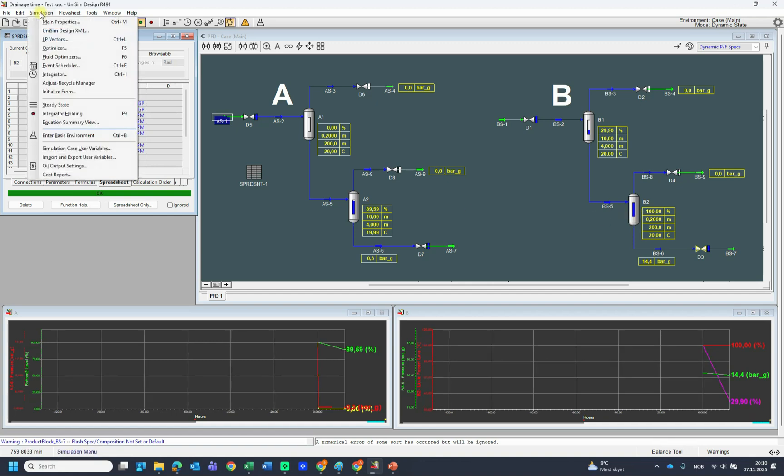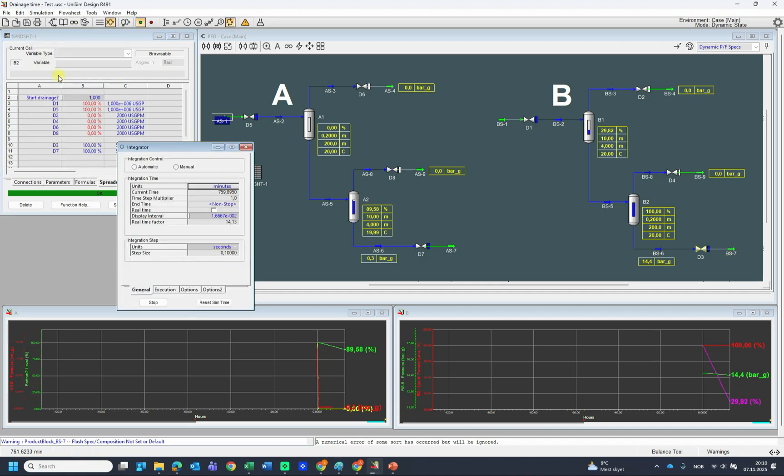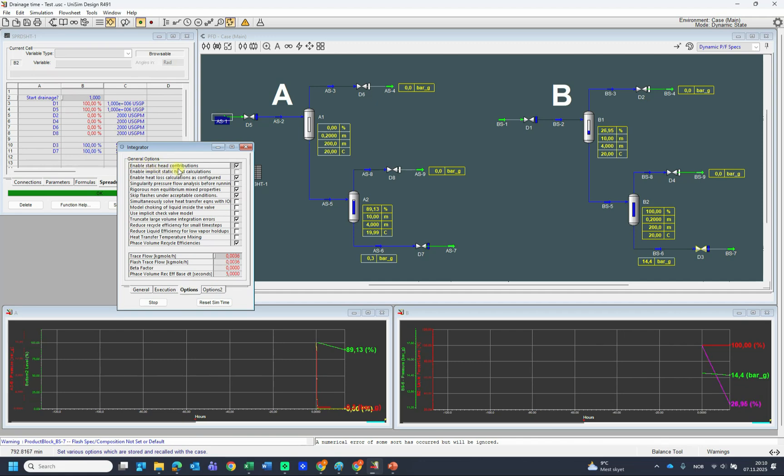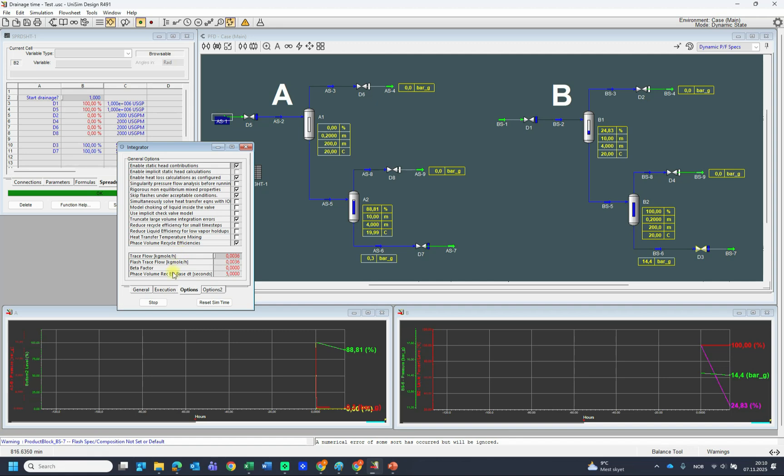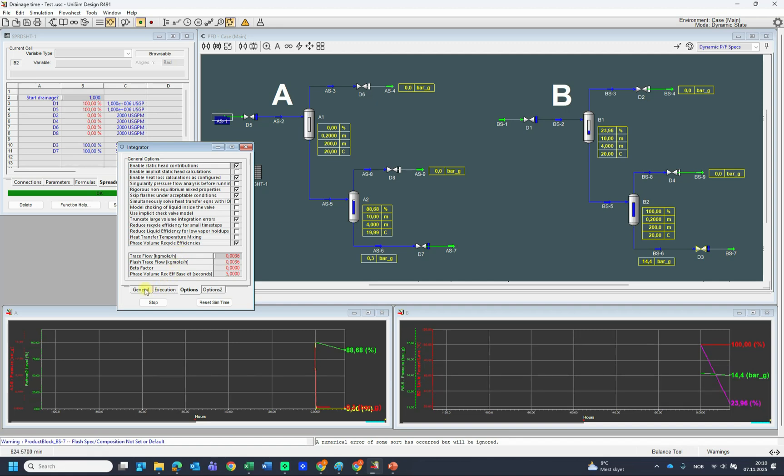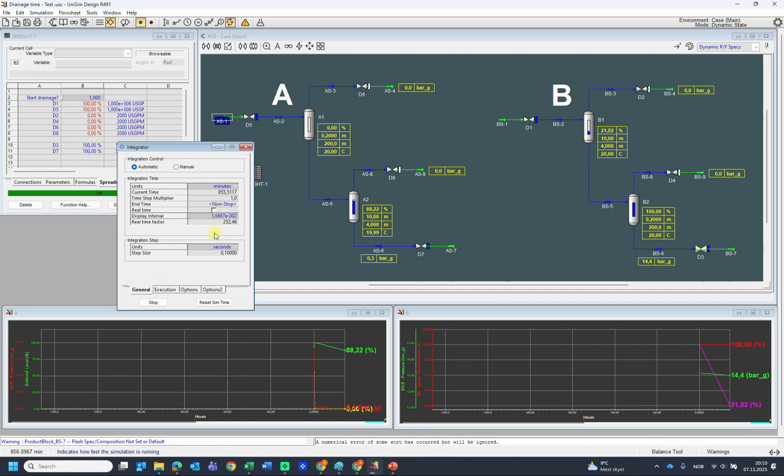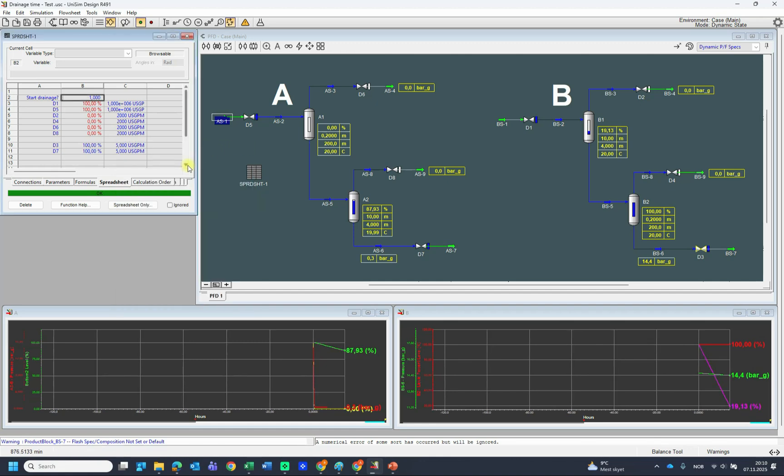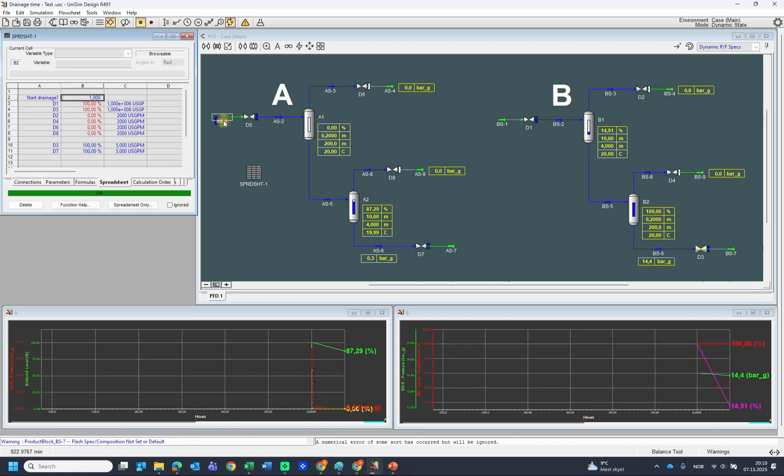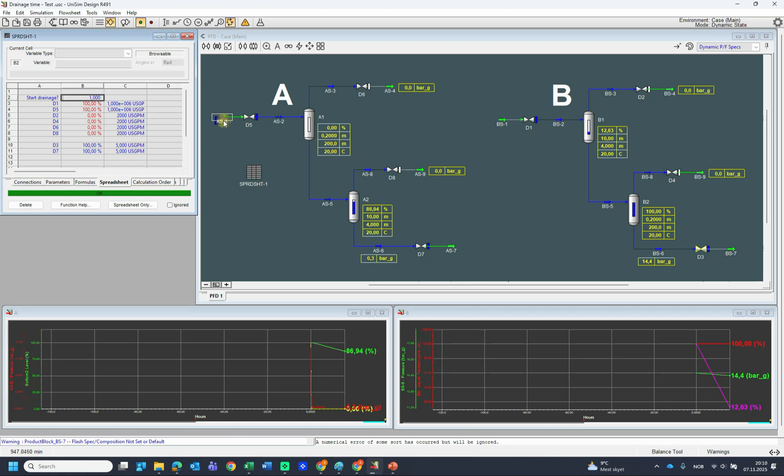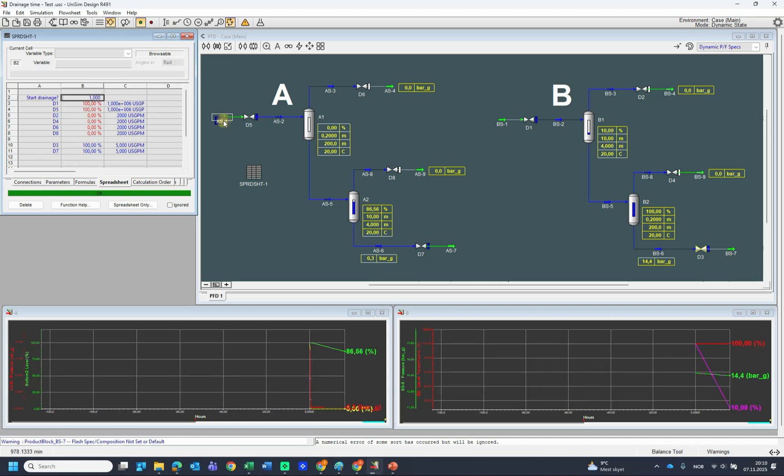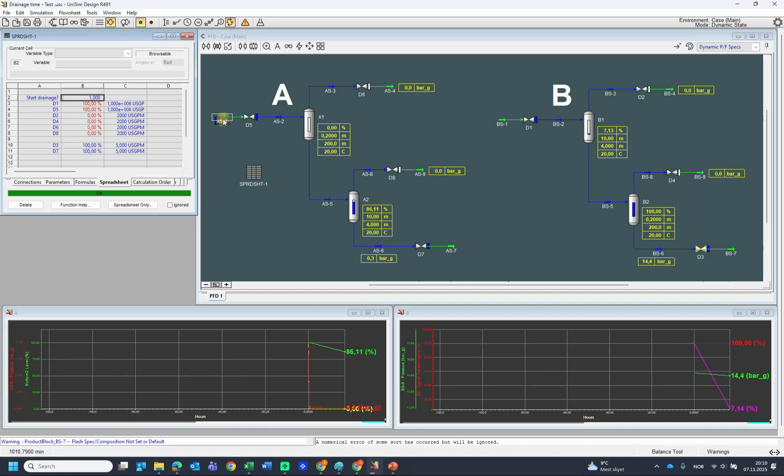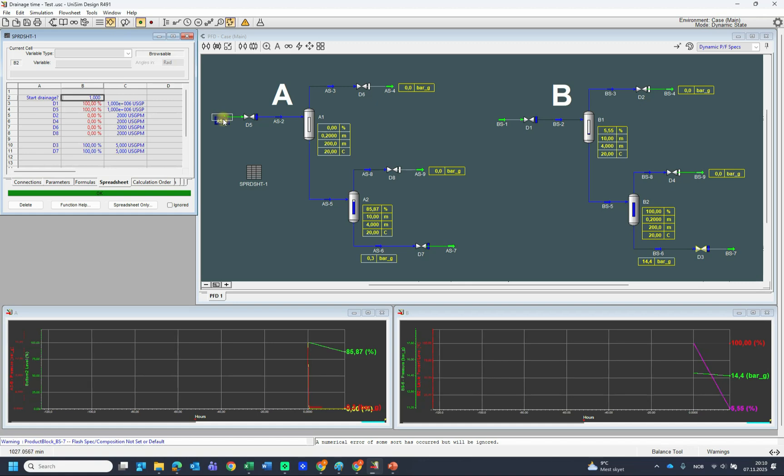And I want to mention something about the simulation. Since that's a dynamic environment, you need to remember always enable the static head contributions, because it is by default not selected in Unisim dynamic. You need to do that. And also the step size I use is 0.1. And also I just indicate, in this case, for simplicity and just using the Peng-Robinson, which is the best property package in Unisim, I just use normal decane as the liquid. But for water it will be the same.